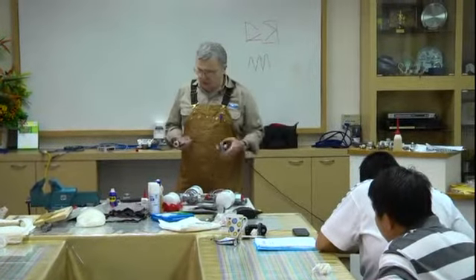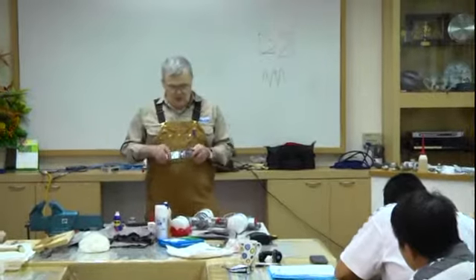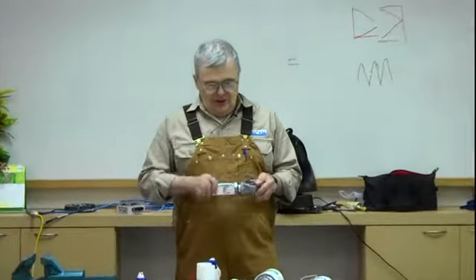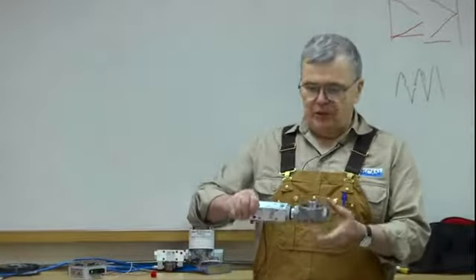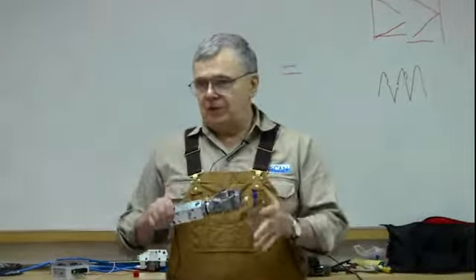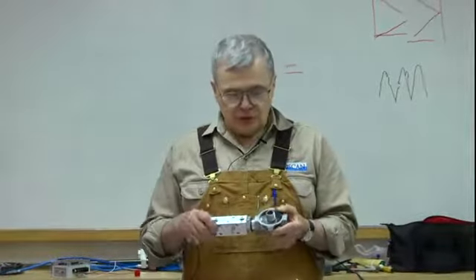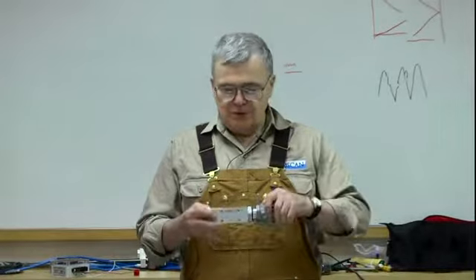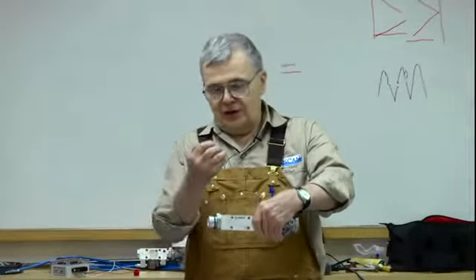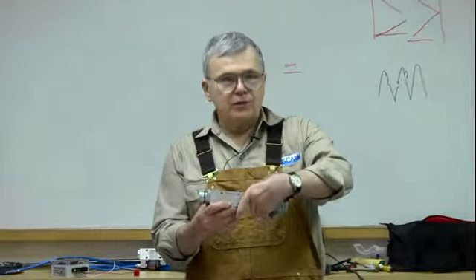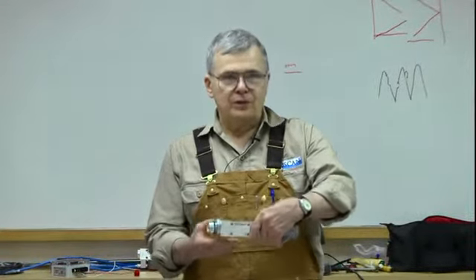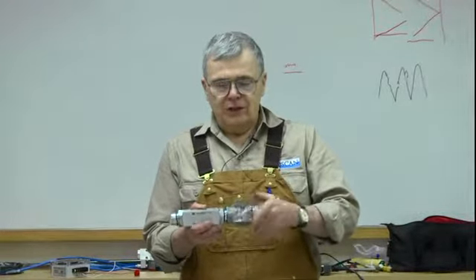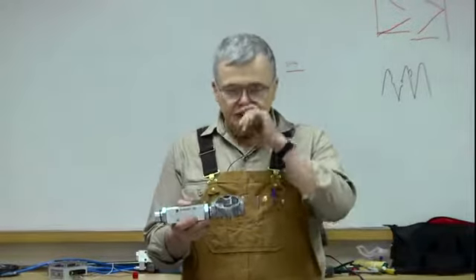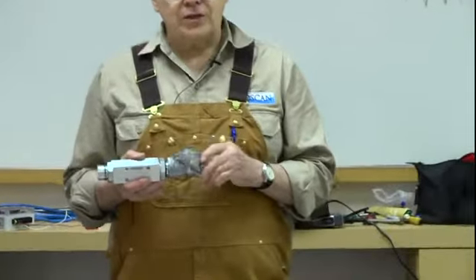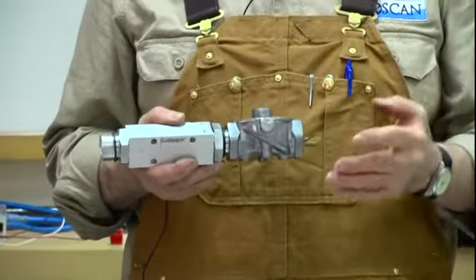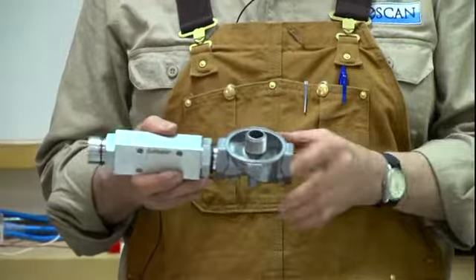If you get into a situation out in the field where you can't get the pulsation damper in, you have to rotate the casting a little bit, either the flow homogenizer or the pulsation damper. We want the sensor to be pretty horizontal, at the very bottom within a few degrees of rotation, no more than 5-10 degrees at the most. But to achieve that, you might have to rotate this casting a little bit. The pulsation damper and the flow homogenizer can be up to about 30, 35, even 40 degrees off center, and it will still work.